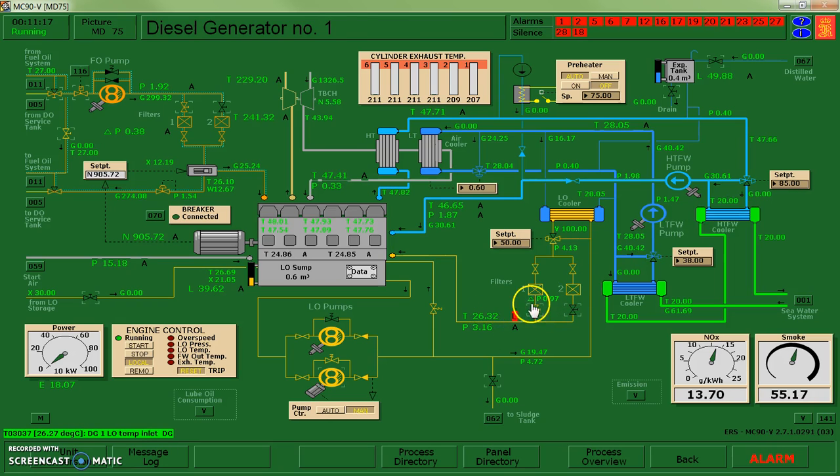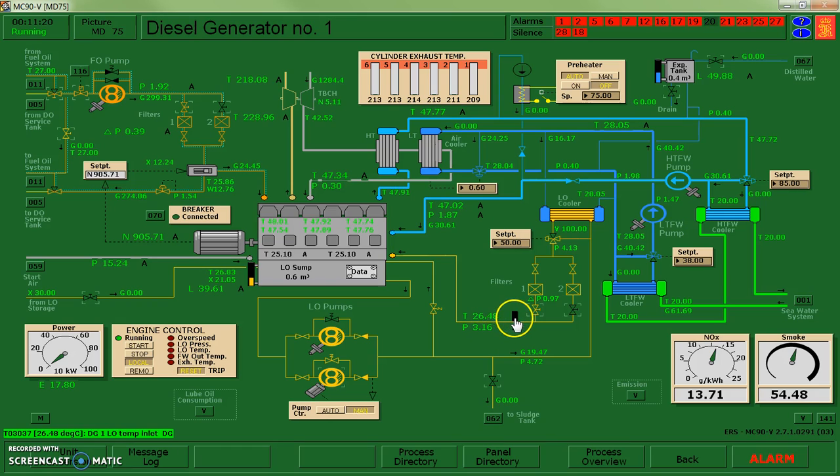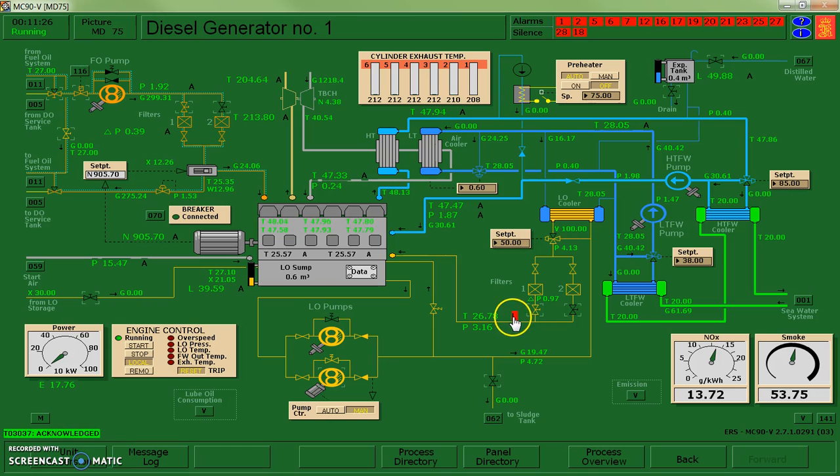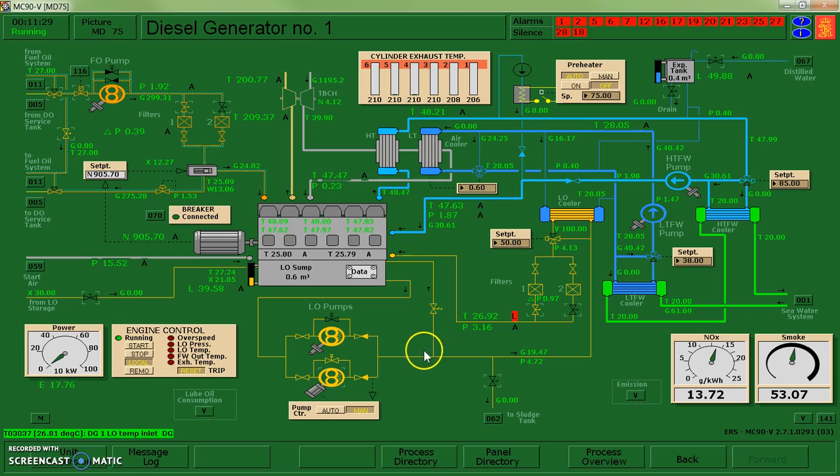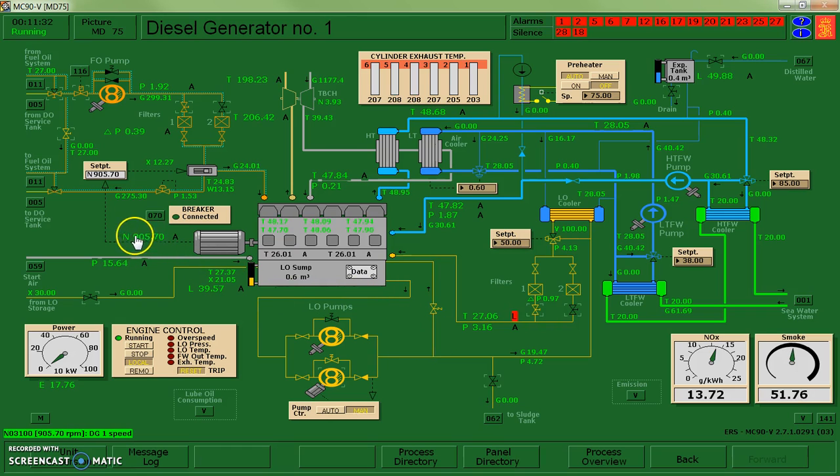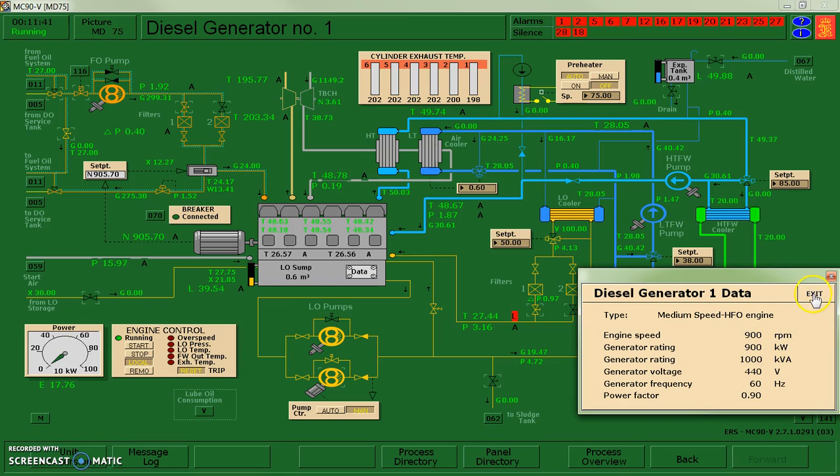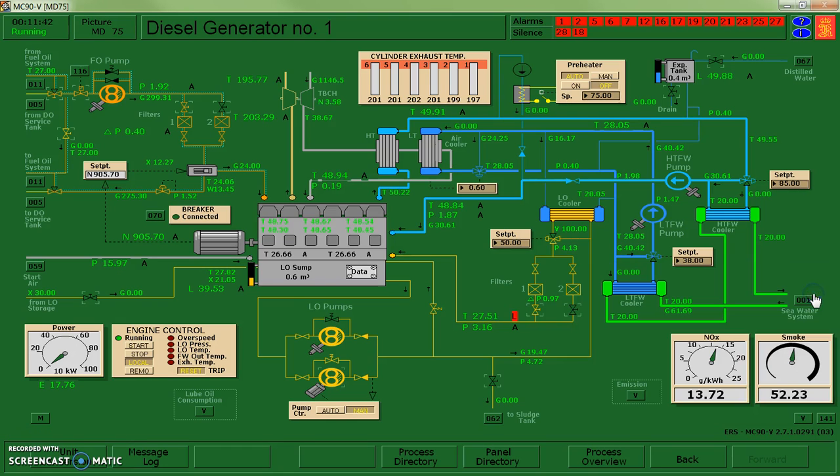You can hear an alarm just went off. This was my lube oil system, telling me that it was not warmed up yet. So it will eventually warm up. And that alarm will eventually go away. It looks like I've stabilized around 905. If I take a look at my data sheet, it looks like this wants to be about 900 RPM for the engine. So I think I'm pretty happy with where it's sitting.